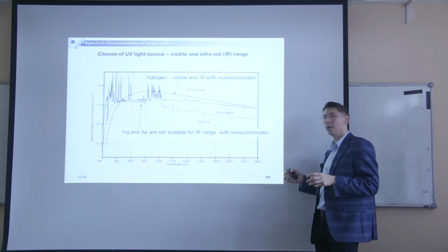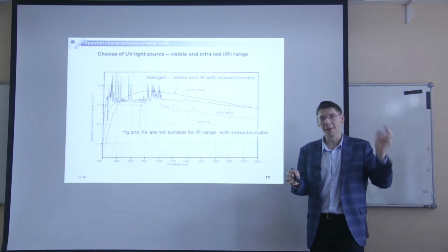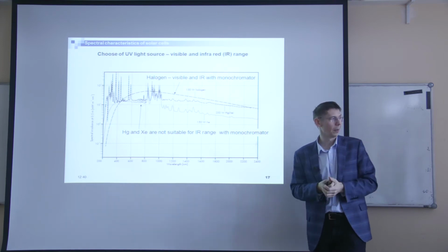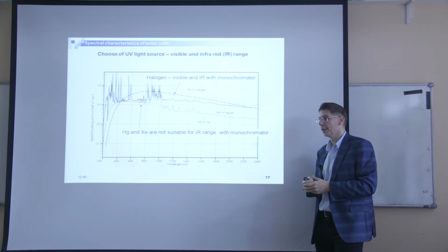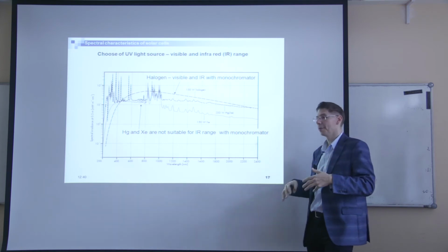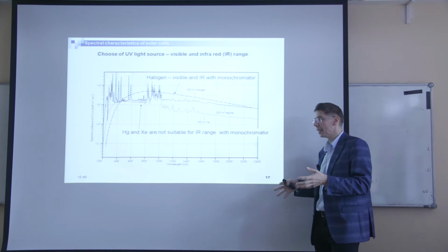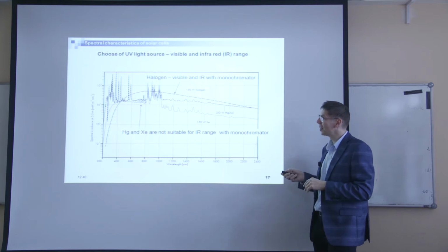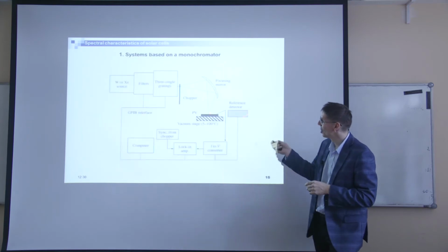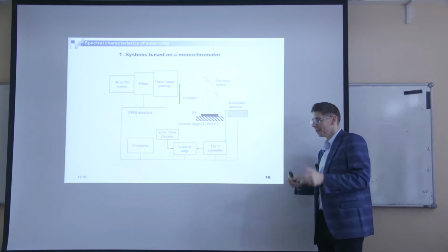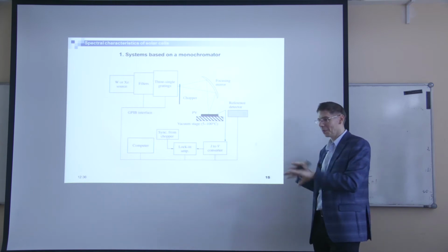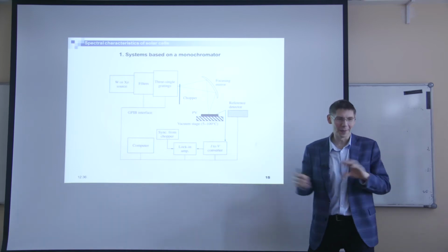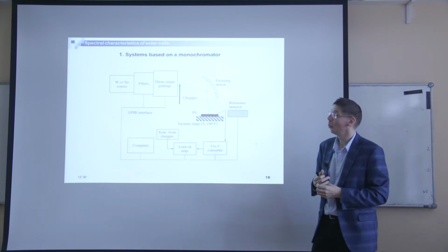If, for example, you open the door or open the window, for example in the winter, you can change the temperature of the measurement room, and it would affect the intensity. So first of all, you know the main rule: during the measurement, don't touch anything, and it's better not to open the window or the door.